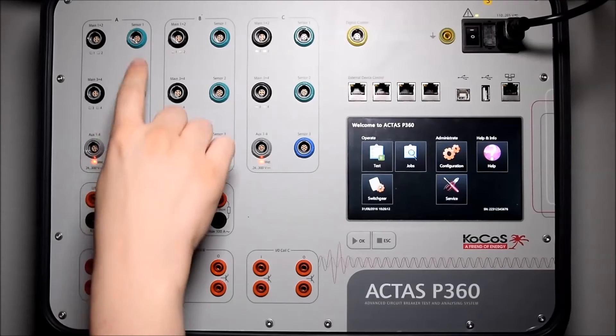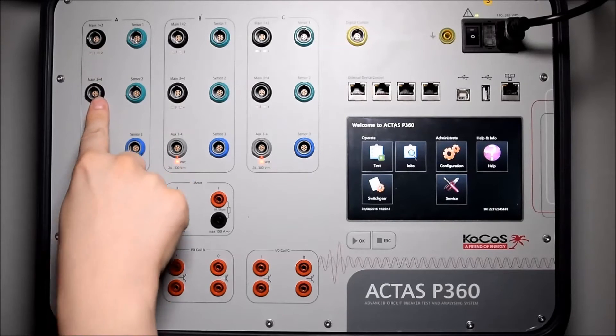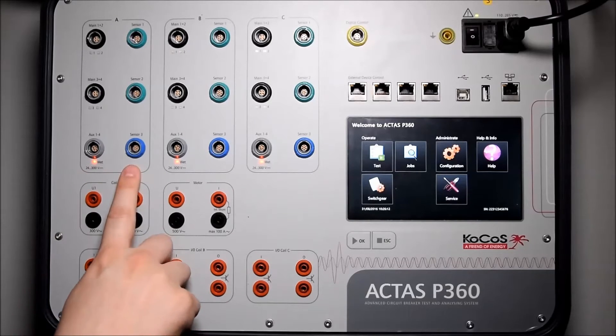The ACTAS P360 is equipped with three pole groups. Each group features four main contacts, two sensor inputs for the connection of linear transducers as well as incremental sensors, four auxiliary contacts with wet and dry functionality, and an additional sensor input for current clamps, voltage, pressure, and temperature sensors.